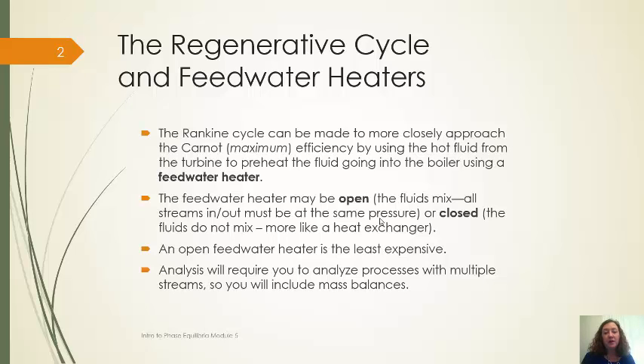An open feedwater heater is the least expensive. Basically, I'm going to take streams at different energy levels and mix them to preheat the material going into the boiler. That is going to require analysis with multiple streams, and it does require that I get the pressures to match of all of those streams.